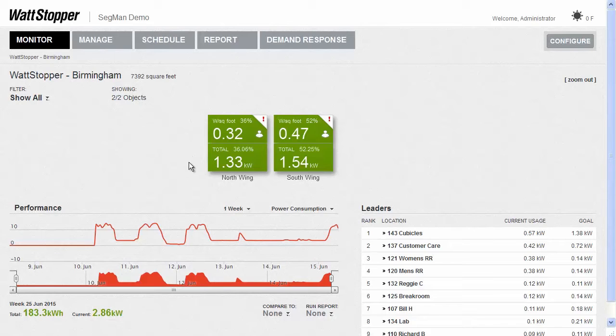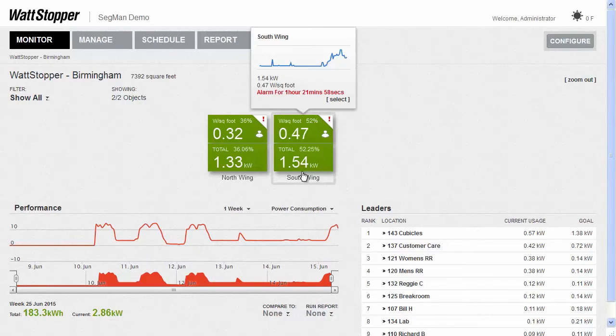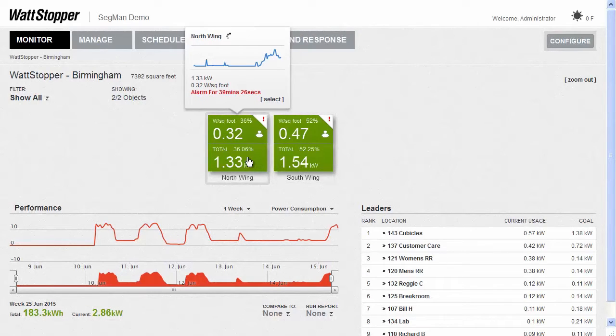We can also put the voltage and an estimated value for the current into any on-off room controllers that don't have current transducers to get an idea of what's happening with them. Notice that each one of these tiles has a slight drop shadow — this subtle hint tells us that this tile is showing us information based on other tiles. When I hover over a tile, I get a spark line, a quick little graph that shows what the power usage has been most recently for this area.